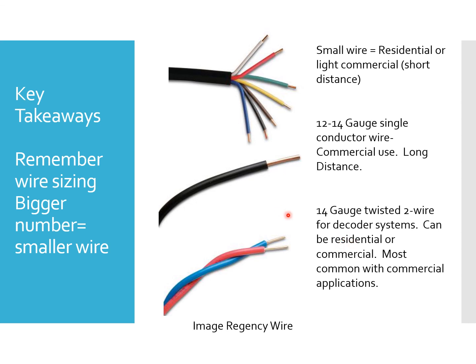So you have to use some common sense here of how far your valve is going to be from your controller. How often will you actually be more than 100 or a couple hundred feet away? So it might not be necessary to do all of these calculations if you have a very simple cut and dry, one valve at a time system. You may just be able to get away with the 18 gauge wire for all residential and then use 14 or 12 for your larger commercial. Now, sometimes you don't have the luxury of choosing which size wire you're going to be using. You're using whatever has been dictated to you on the irrigation plans.